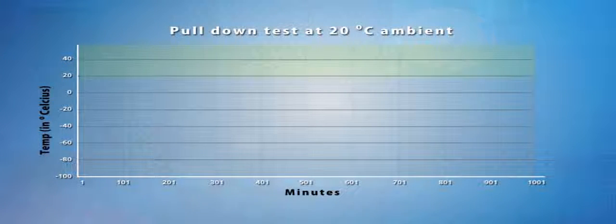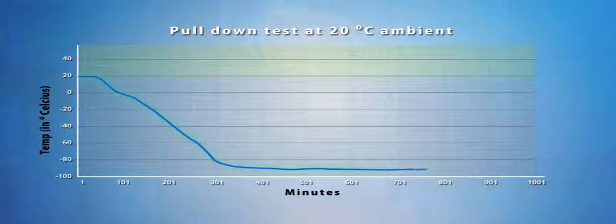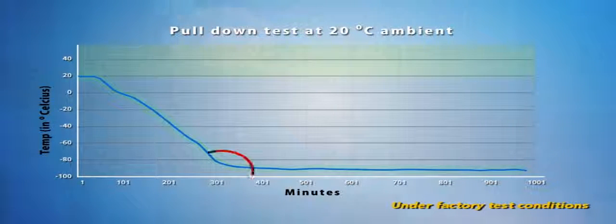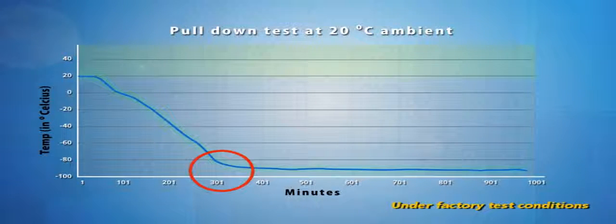Pull down time is the temperature required to lower the temperature of the ULT freezer from ambient to the set temperature. Esco ULT freezer can achieve 306 minutes pull down time from 20 degrees Celsius to minus 80 degrees Celsius under factory test conditions.